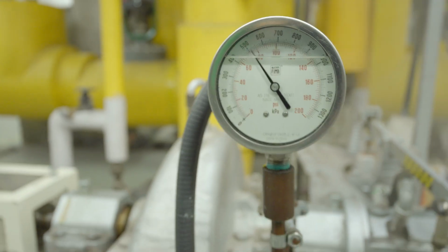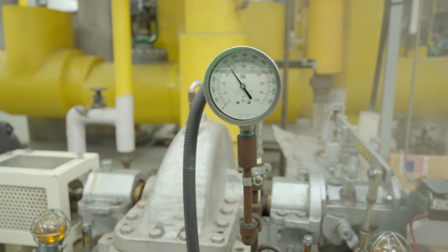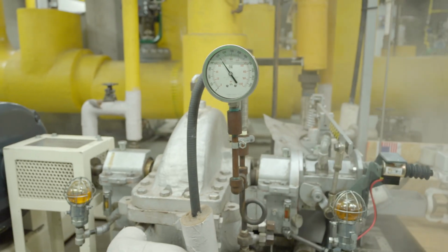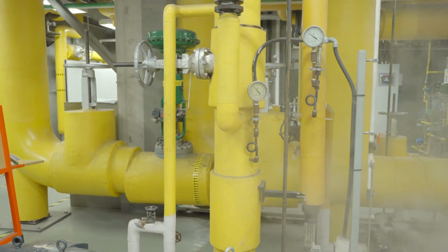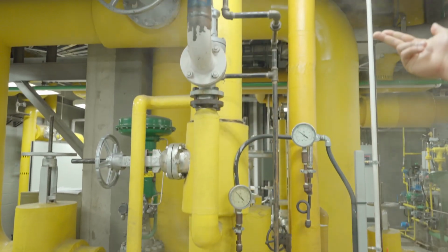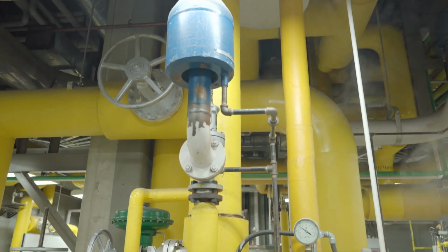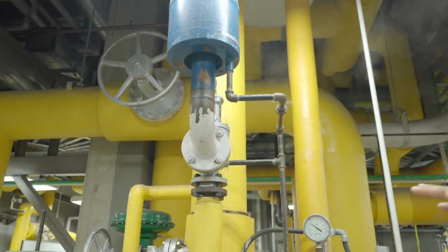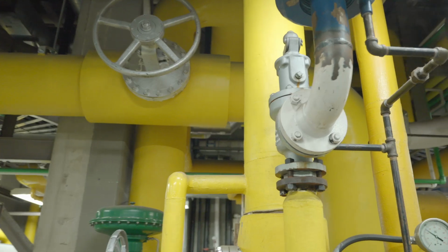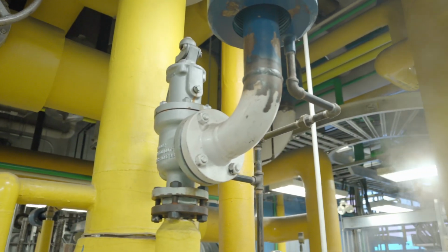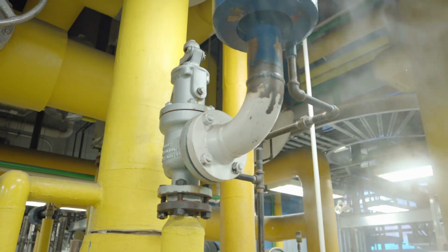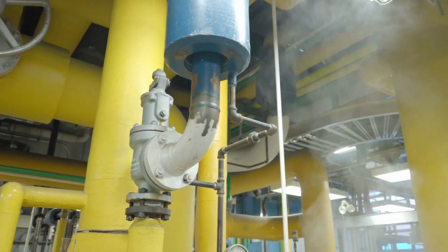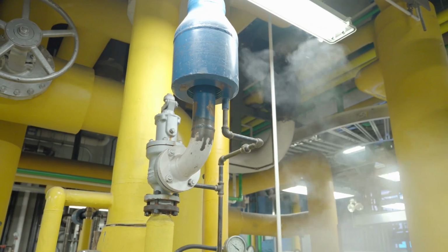Obviously, maintaining the pressure is important. We don't want to overpressure the components, as they're only rated to a certain point. One of the other components we have on the low pressure header is our pressure safety valve on the back here. So in the event that we start pushing too much pressure into the low pressure header, and any of the systems aren't prepared to compensate for it quickly, that'll be the blow-off valve that releases to relieve some of the pressure so we don't cause any damage to the lines or to any of the fittings.